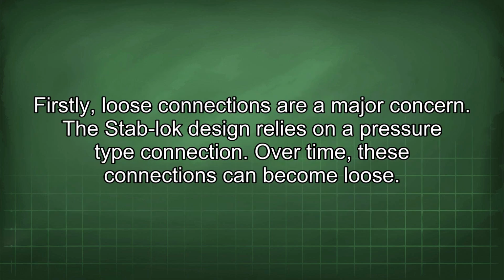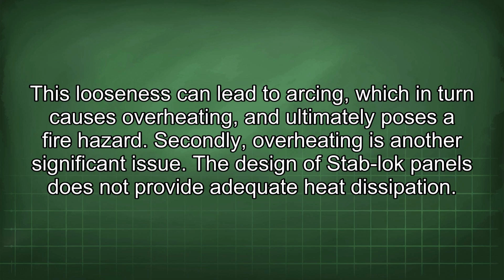Firstly, loose connections are a major concern. The Stab-lok design relies on a pressure-type connection. Over time, these connections can become loose. This looseness can lead to arcing, which in turn causes overheating and ultimately poses a fire hazard.